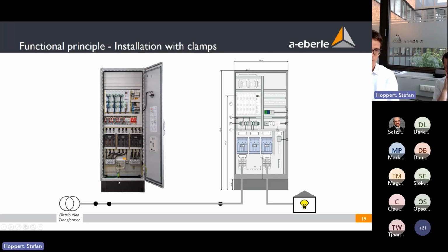Our target is to make it as easy as possible. So you enter the cabinet from below, and you connect the cables directly on the clamps on the input side, and you connect the cables on the output side. That's all you have to do after you have installed the cabinet in the proper position. Then you switch the system on and it's working. Here on the drawing, you see it again. The cable is coming from the line where the distribution transformer is connected. Here is your connection point to the grid, and then it's connected to the clamps here on the input and here on the output side. That's it. For us, it's necessary that it's easy to install, and you don't have to do a lot of things afterwards.